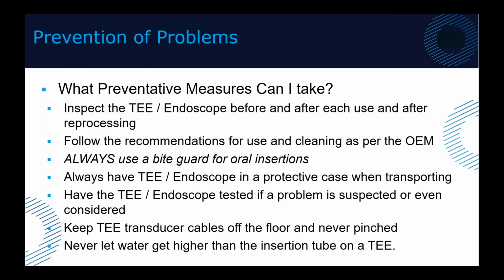Follow recommendations for use and cleaning per OEM. That means the chemicals that you're using to process, make sure they are approved. Using non-approved chemicals is one of the fastest ways to kill transducers for sure, and endoscopes as well.